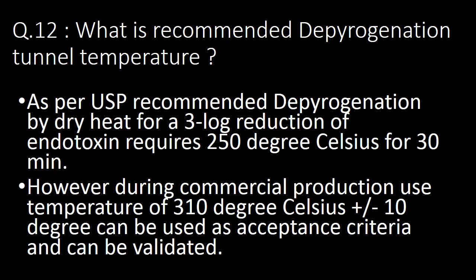12th question: what is the recommended depyrogenation tunnel temperature? As per USP, recommended depyrogenation by dry heat for a 3-log reduction of endotoxin requires 250 degrees Celsius for 30 minutes. However, during commercial production, a temperature of 310 degrees Celsius plus or minus 10 degrees can be used as acceptance criteria and can be validated.